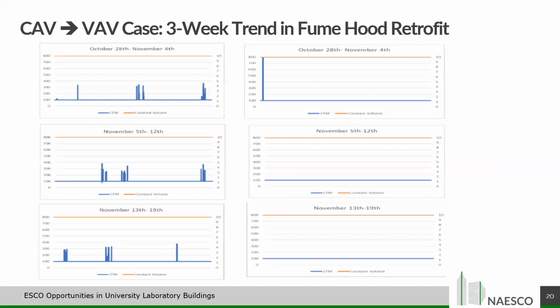Next. My favorite part of coming up with this data is basically the pre and posts. And just to show you here, the chart to the left is hood number 1. The chart to the right is hood number 2. Basically, the orange line on the top part of the chart symbolizes constant volume. In this particular case, 800 CFM, on a 6-foot hood running 24 hours a day, 7 days a week. Once we do the conversion, again, as mentioned previously, we're able to reduce that exhaust by 85% by converting the existing infrastructure.